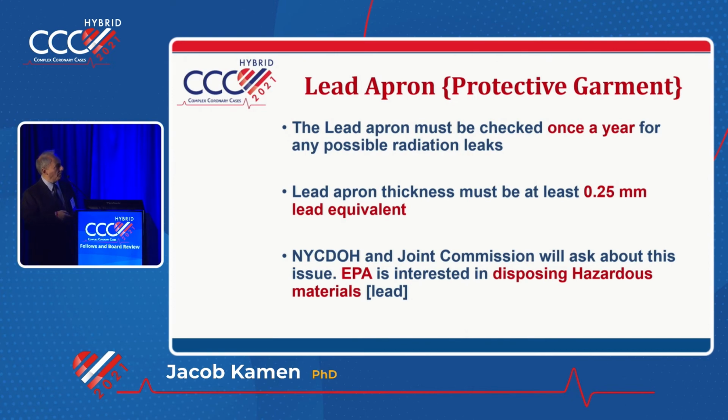Lead apron. The new regulation, they changed the name to protective garment. Can anybody tell me why? They hated the word lead? No, because the new lead apron is not made of lead. It's made of composite material, which is about 20% less weight on you, and it gives you the same protection. But when you bend it, it breaks. Do you follow me? Lead is nicely bent, but the composite material is bismuth. It breaks when you bend it.